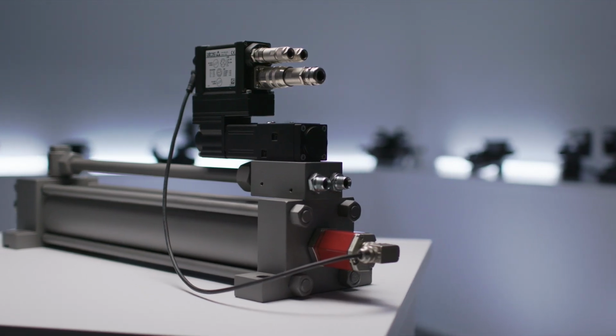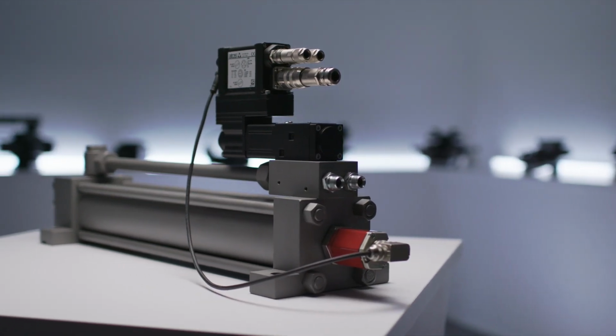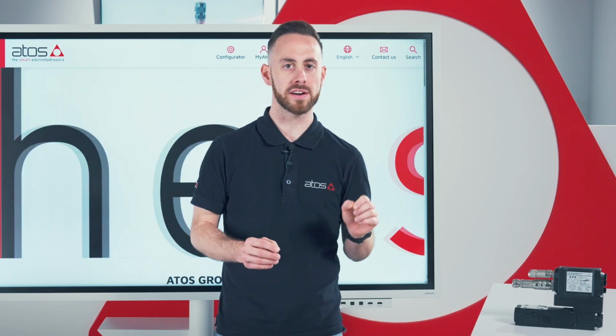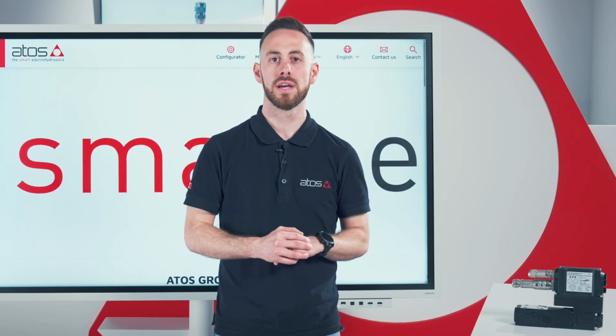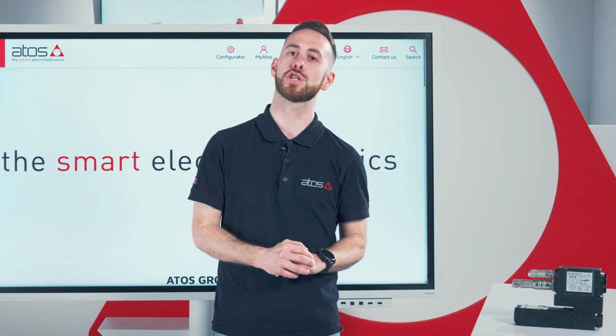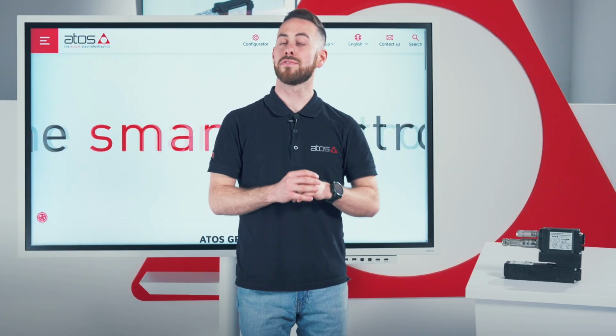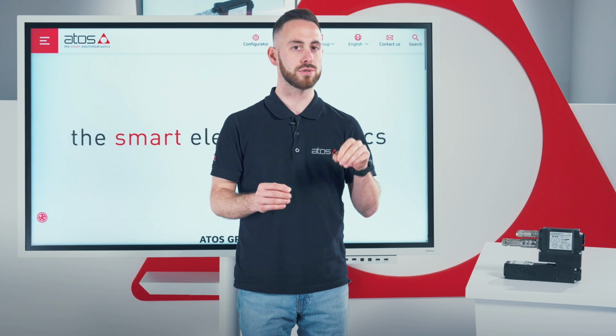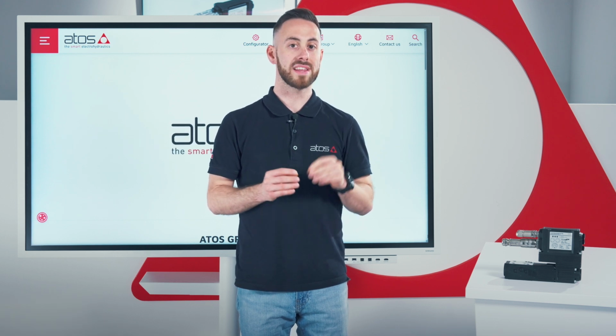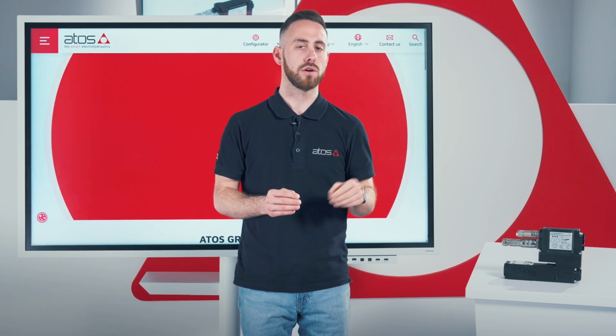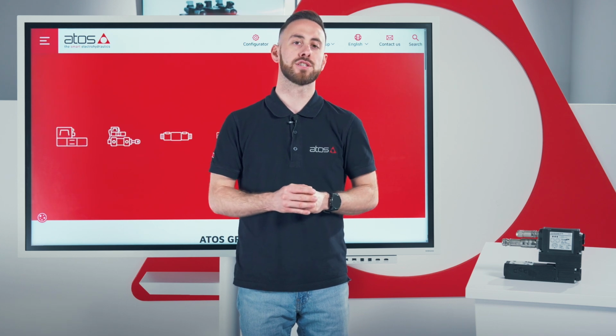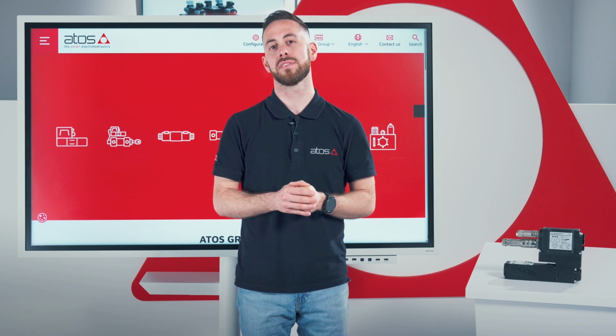An axis controller is an electronic device that manages and controls the position of a linear or rotary hydraulic actuator that moves a specific part of the machine. These devices use the feedback from a position transducer installed on the actuator to control with high accuracy the position of an axis or a motor, acting on the spool opening of a proportional valve.